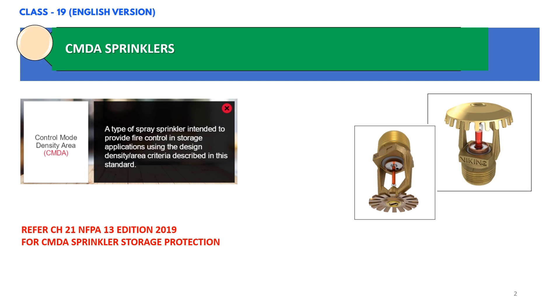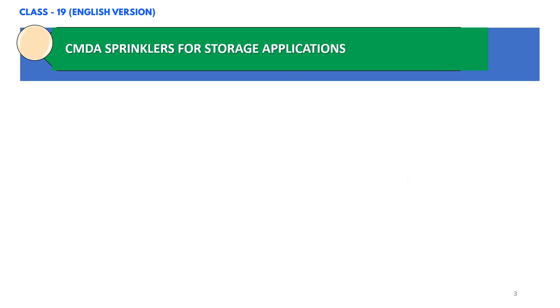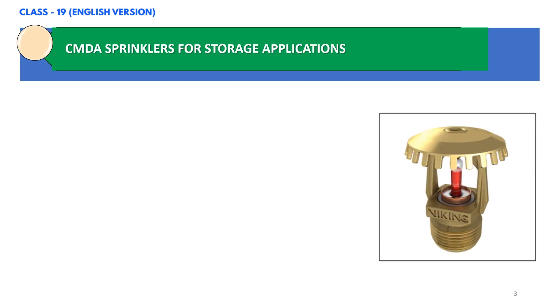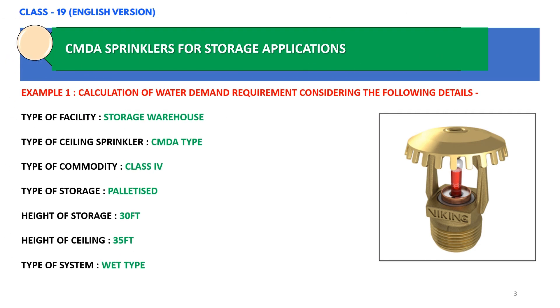You can refer to chapter 21 in NFPA 13 2019 edition for more details. Now let us see an example to calculate the water demand. CMDA sprinklers are used to control fires in storage applications. In this example, the type of facility is a storage warehouse, the type of ceiling sprinkler is CMDA type, commodity classification is Class 4, storage type is palletized storage, height of storage is 30 feet, and height of the ceiling is 35 feet. The type of system is wet type.